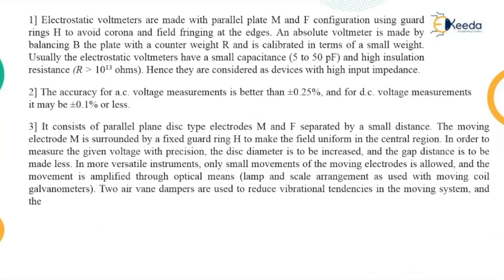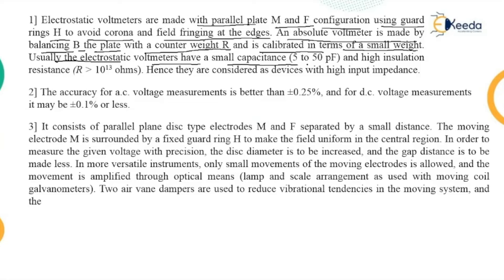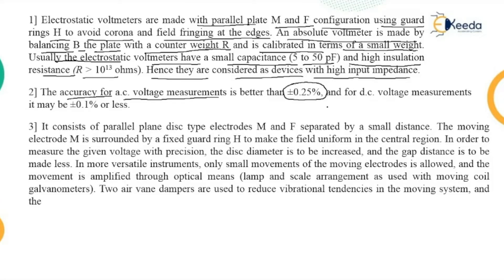Electrostatic voltmeters are made with a parallel plate M and F configuration using a guard ring H, to avoid corona and field fringing at the edges. An absolute voltmeter is made by balancing the plate with a counterweight R and is calibrated in terms of small weights. Generally, electrostatic voltmeters have a small capacitance of 5 to 50 picofarads and a high insulation resistance greater than 10 to the power 13 ohms, making them devices with high input impedance. The accuracy for AC voltage measurement is ±0.25% and for DC measurement it is ±0.1% or even less.